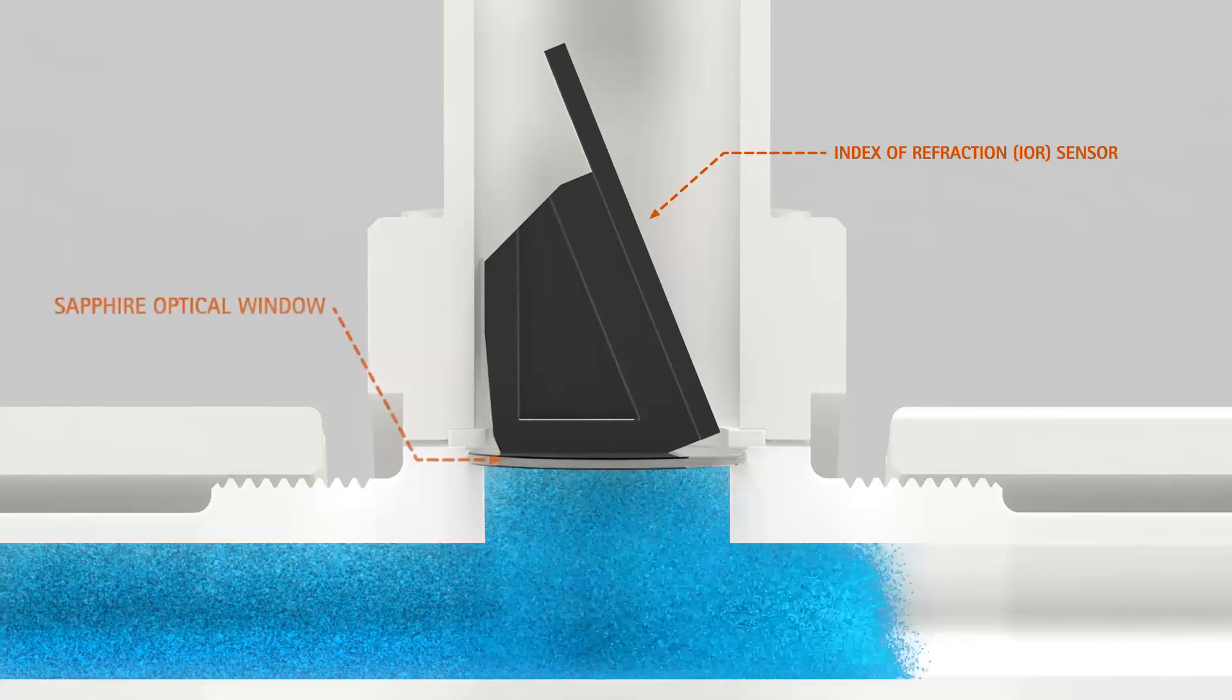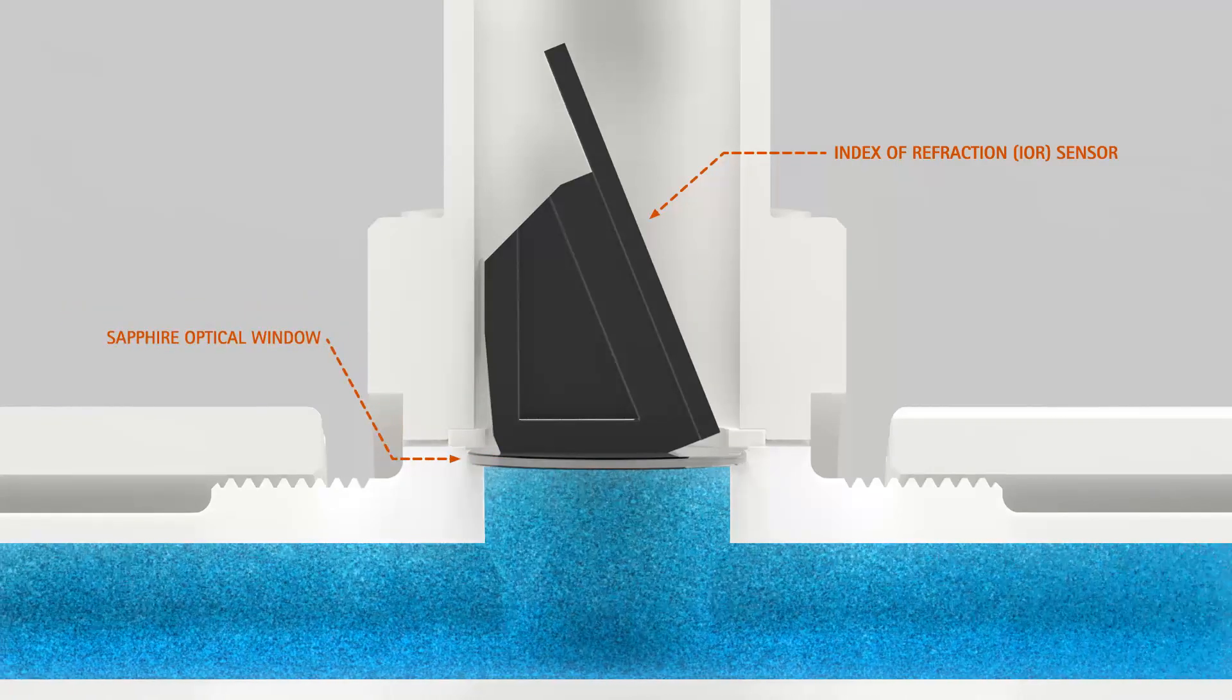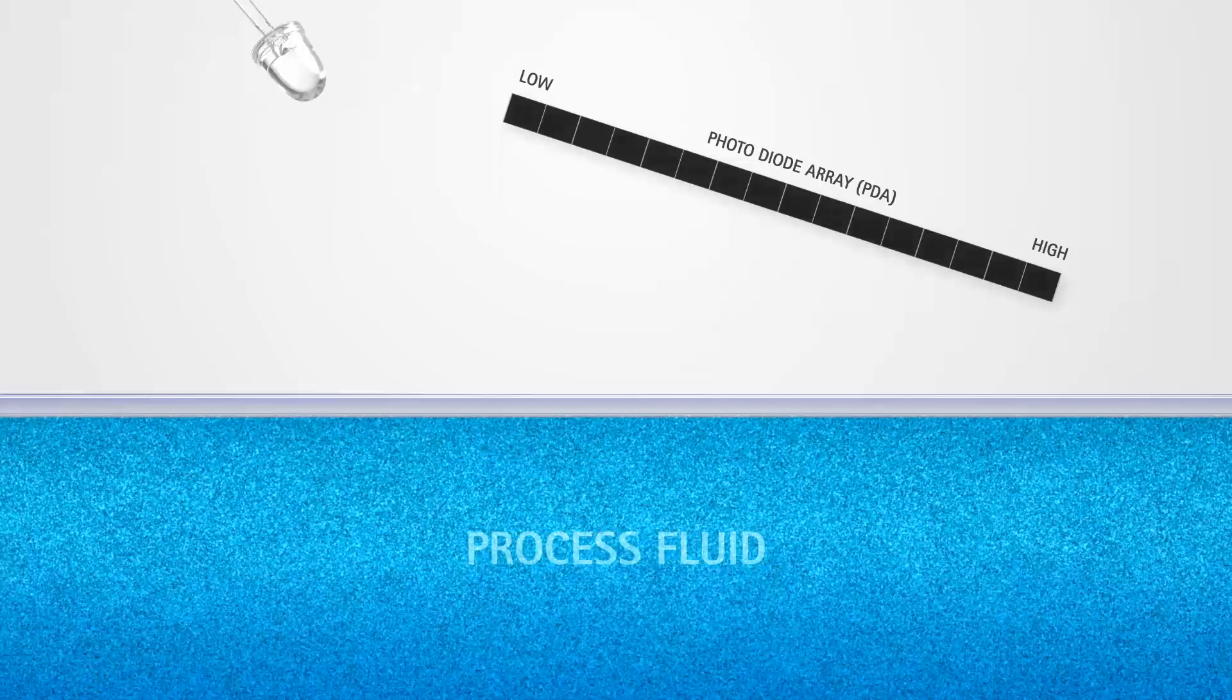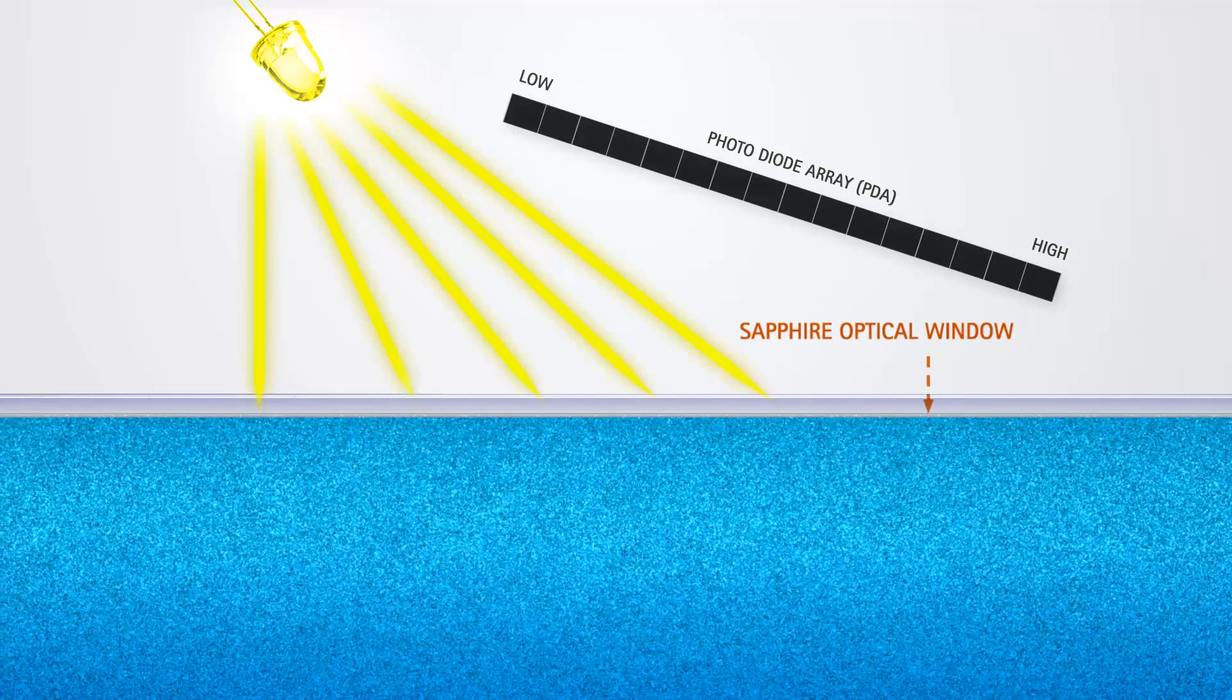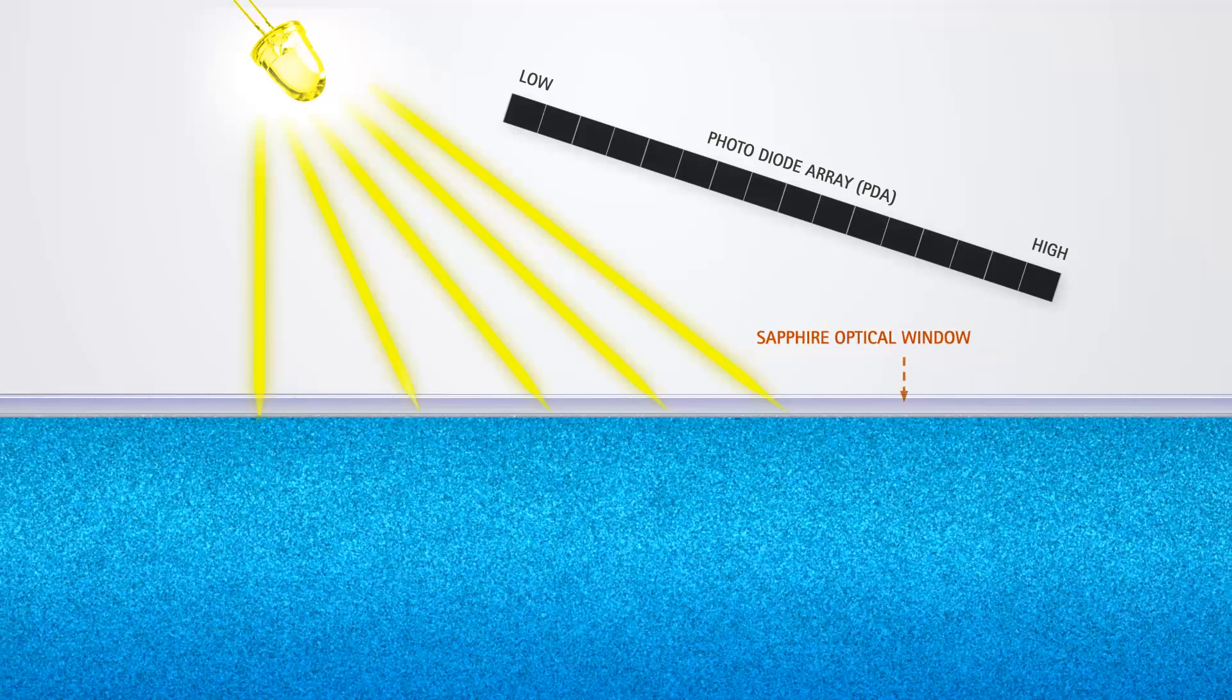The Integris Concentration Monitors utilize Index of Refraction as a direct measurement of how light reflects off the fluid while in contact with an optical window. This measurement is directly correlated to a chemical's concentration. To illustrate, here a light-emitting diode, or LED, shines light onto a sapphire optical window in contact with the liquid.